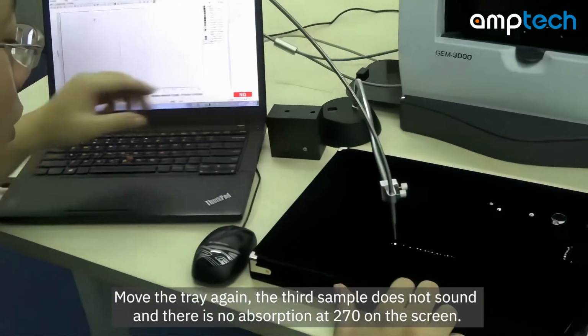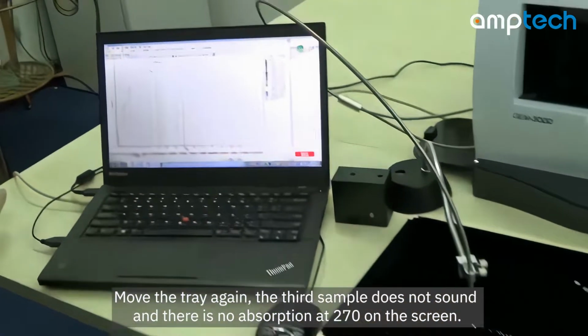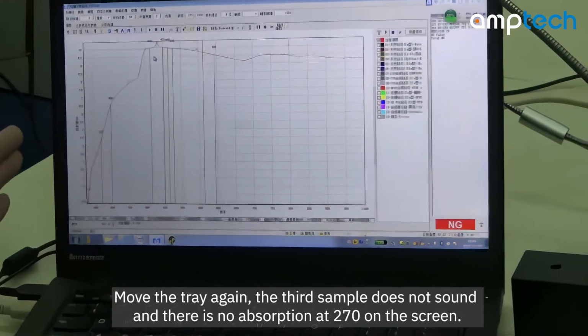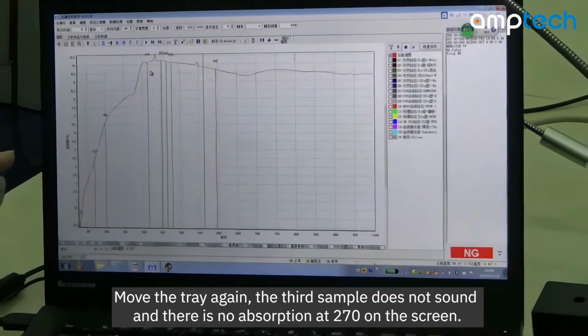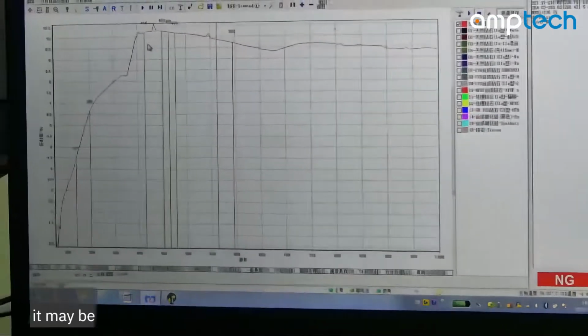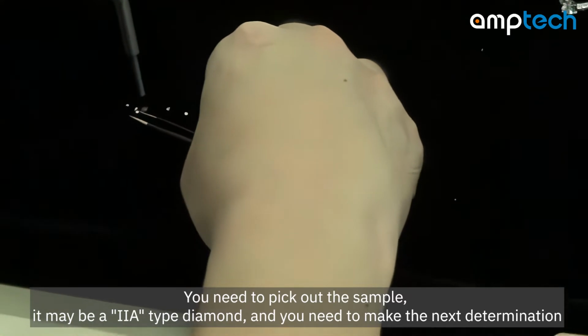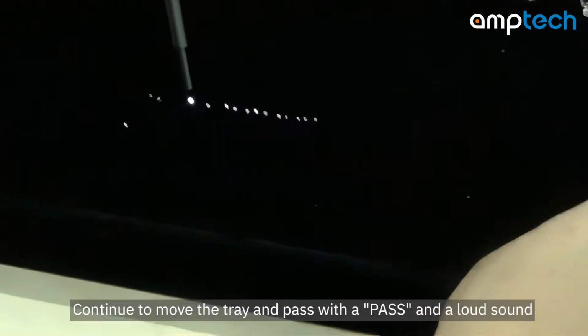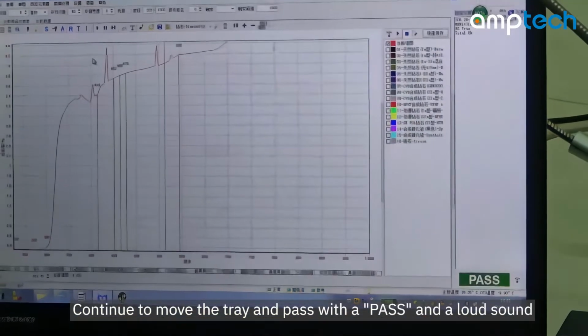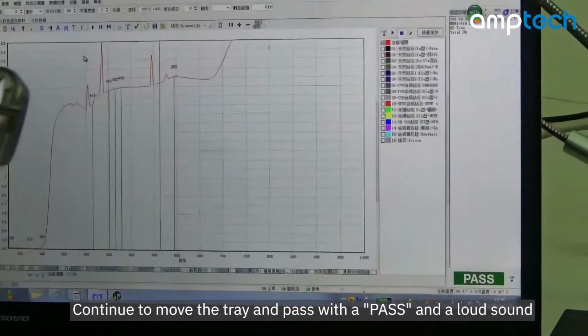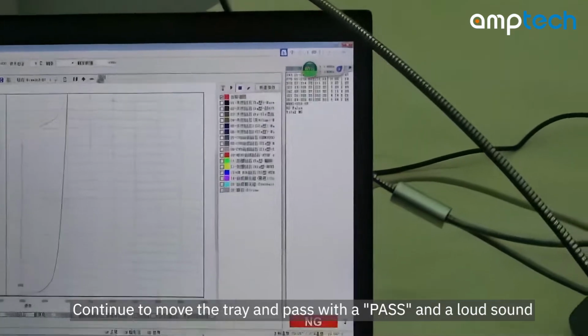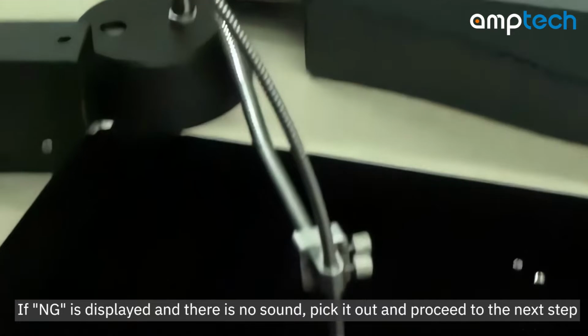Move the tray again. The third sample does not sound, and there is no absorption at 270 on the screen. You need to pick out the sample. It may be a type 2A diamond, and you need to make the next determination. Continue to move the tray and it passes with a loud sound. If NG is displayed and there is no sound, pick it out and proceed to the next step.